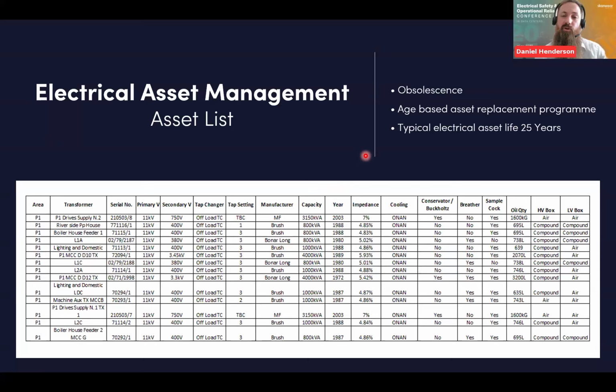And then finally, if you're looking at a replacement process or putting some proposals together, you might start looking at age-based asset replacement. If you've got year of manufacture for switchgear or transformers, you can try and group these and identify all your older assets, check for any safety considerations, and make a decision from there. It might be that in 5 years you replace these, 10 years you replace those, until you establish that life cycle asset replacement process, which might not yet exist in your business.